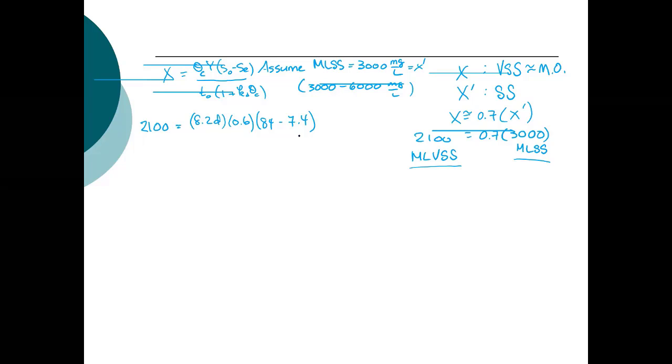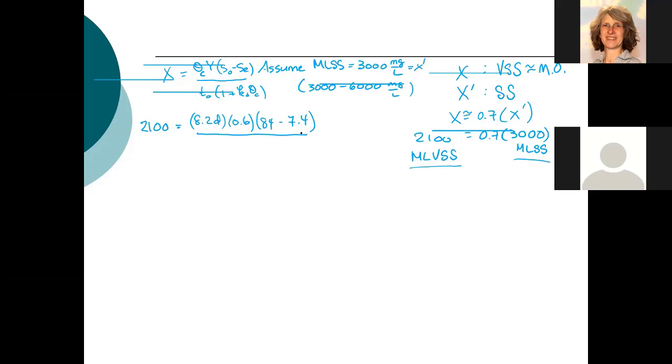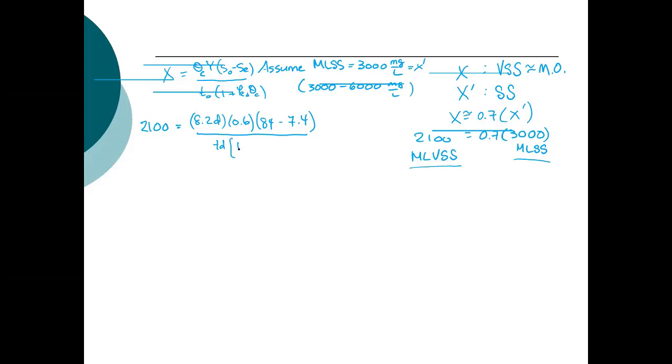and think of the system as the aeration tank and the clarifier, divided by the detention time times 1 plus 0.05 times 8.2, and the detention time is equal to 3.05 hours or 0.127 days.